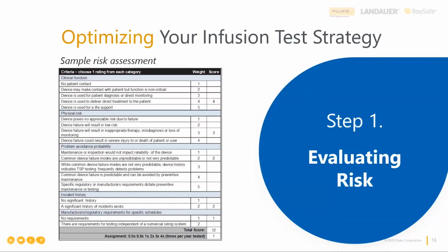So in this case, when the risk is 10 or higher, then what we're looking for is twice per year. If it's in the medium range between 8 and 10, then what we're looking for is once per year. In the case of infusion devices, it's never going to be any lower risk than that. So we're either going to look at it annually or twice per year.